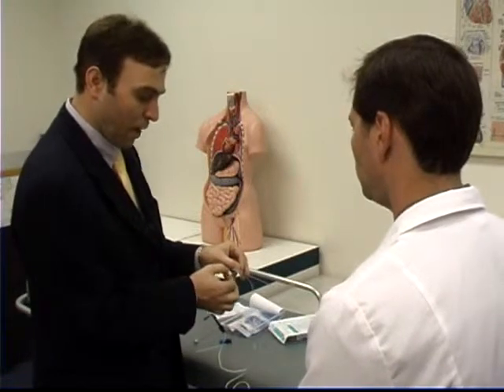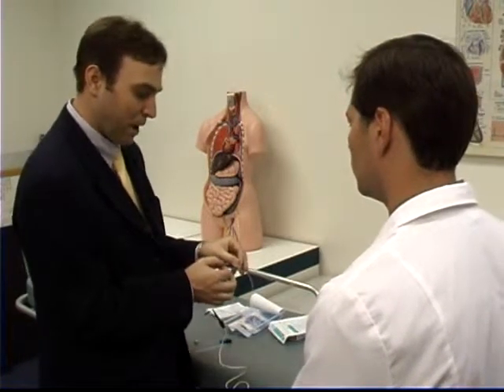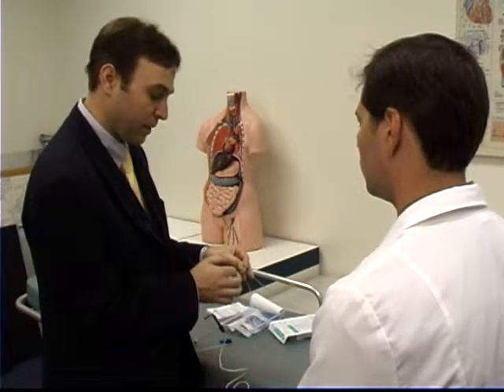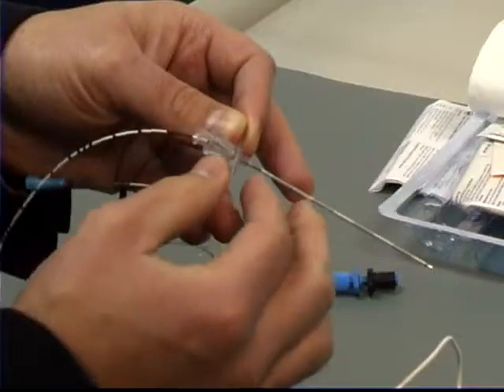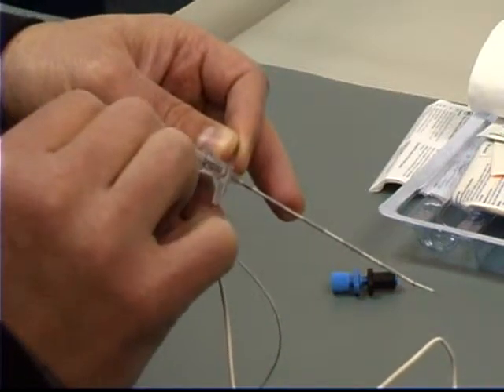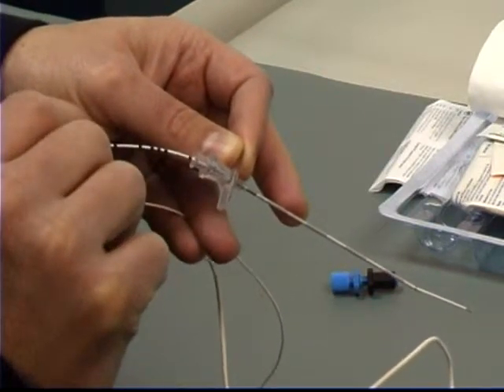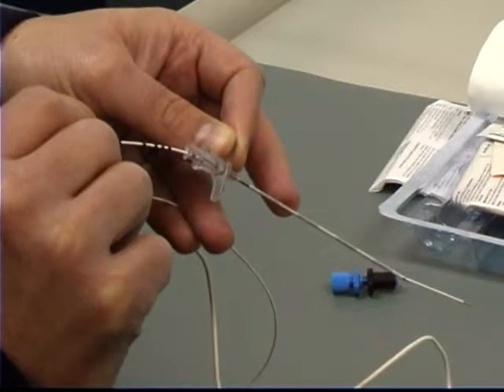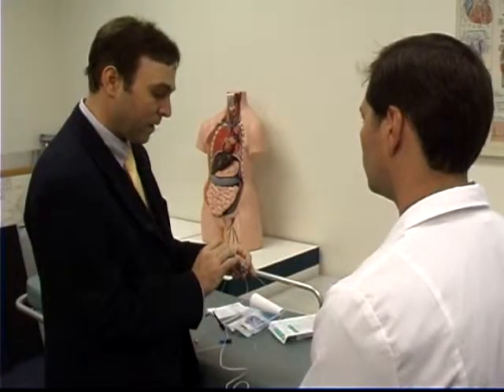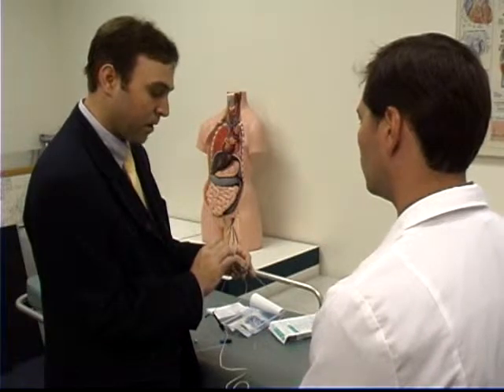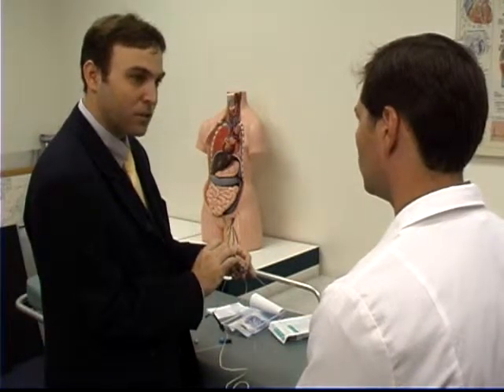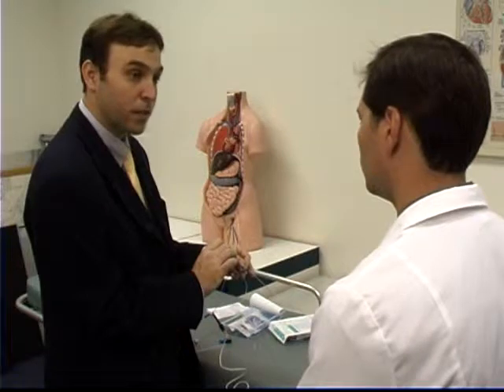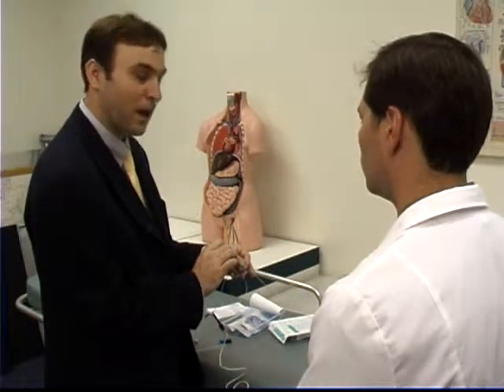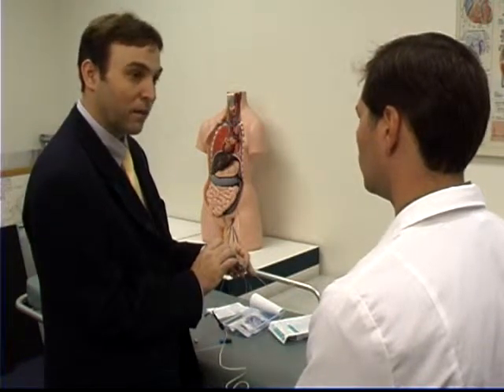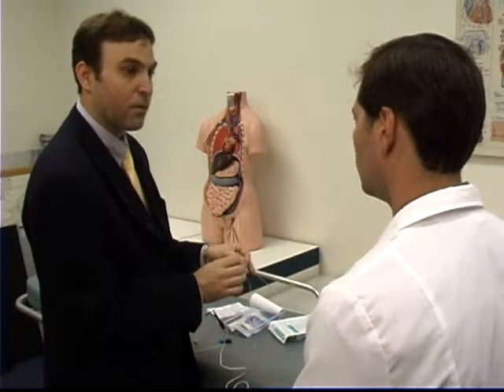Okay. So going back to the catheter, the wide band, again, we're still not yet stimulating via the catheter. We're still stimulating via the needle. Our goal is to advance the catheter 3 to 5 centimeters, maintaining the same level of stimulation that we had prior using the needle. As we begin to advance the catheter, we may maintain that same stimulation, but inevitably you'll lose stimulation probably greater than 50% of the time. And the reason is that we believe that the catheter is moving away from the nerve.